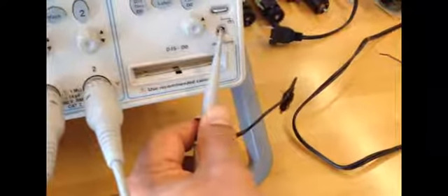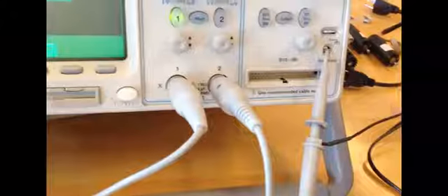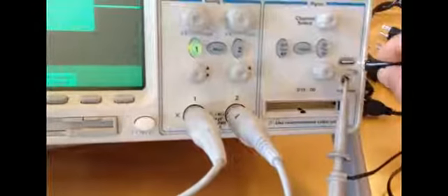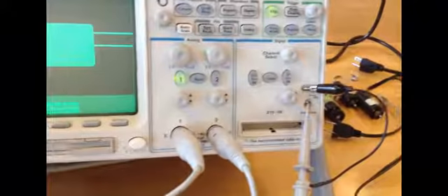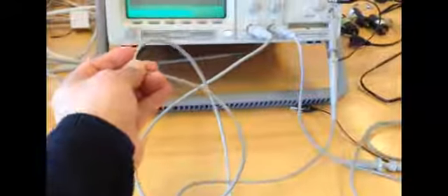So this is used for calibration. I'm going to connect it to this point, and then I can connect the ground even though I don't have to, but I'm just going to show you this is the way that we connect the other one to the ground. But again, I didn't have to because it's already connected. The ground is connected inside. So right now channel 1, as you can see, is connected to a signal.